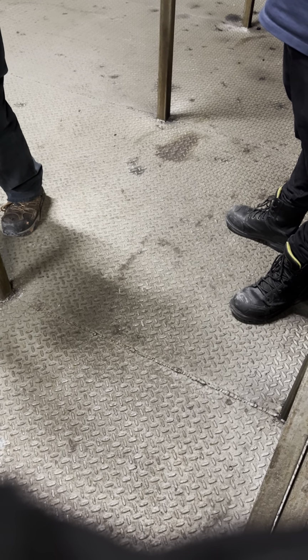and 5 minutes later it tripped again. So I'm looking at everything, trying to figure it all out, and it actually worked out that when I opened up the door and noticed where the freeze alarm was, there was a nice crack in the insulation. When these units run, they will try to get air from wherever they can, whether it's through the door, even though I had all the louvers here sucking all the air into the air handling unit, they still were trying to get it. So that crack was letting air hit that spot, and kept dripping.